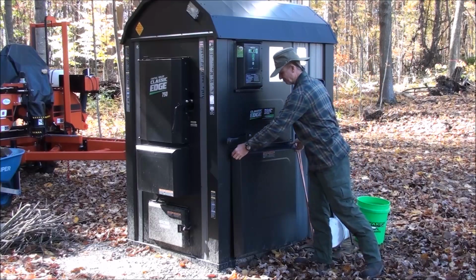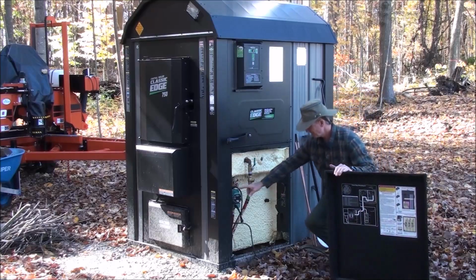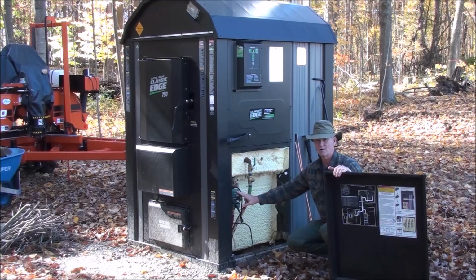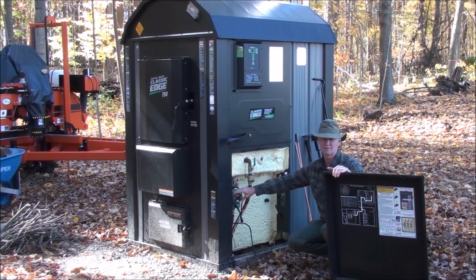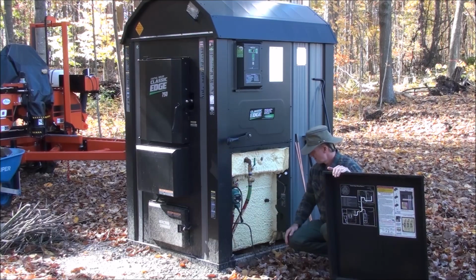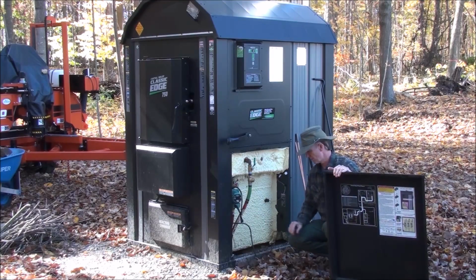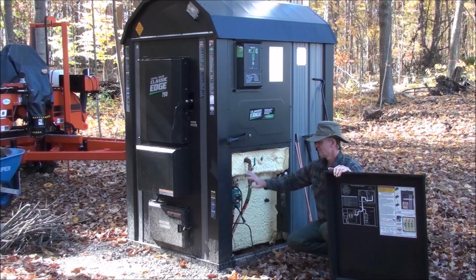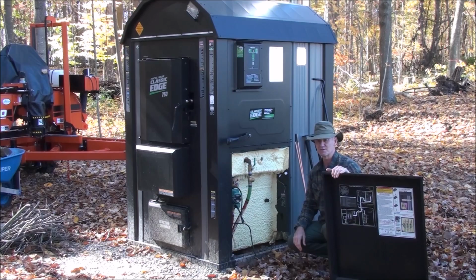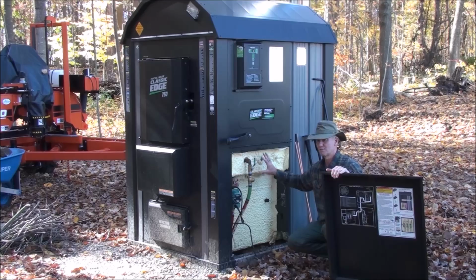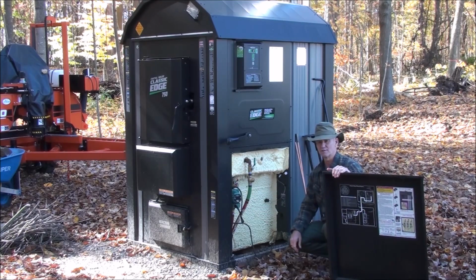And then under this cover here is the pump that moves water to the house to basically a water-air heat exchanger. This pump is moving the water that actually heats your forced air up, in our case. A couple of PEX lines here, supply and return through the house. And there are two outlets in here for the pumps. So when you start it up, it calls for not having this pump running, which is to say it's unplugged, until the roughly 300 gallons of water that are in the system is brought up to 150 degrees. So once we light fires, get the water in this up to 150 degrees, then we'll plug in the pump, which will start moving water to the house, heating the house, and thereby providing a heat load for the outdoor wood boiler to satisfy.